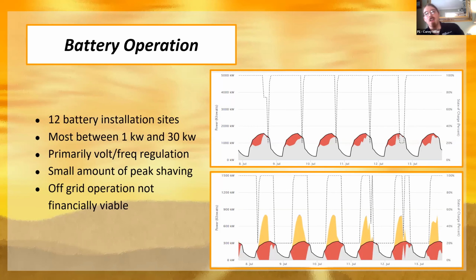These were sized by doing a building load analysis for each site through REOPT. Most of these sites are in the teens to mid-20s in terms of kilowatts, except for the desert lot, which is 150 kilowatts. These were sized primarily for voltage and frequency regulation, with a small amount of peak shaving in some of the larger sites.